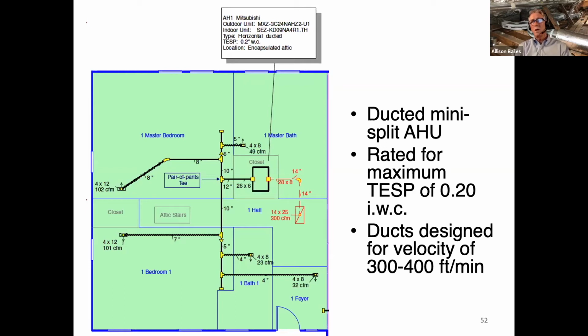It also means if you're not designing for this low velocity, you should make sure that your ducts are in conditioned space or semi-conditioned space. Mine are in an encapsulated attic. Well, nobody would ever put them into an unconditioned attic, right? Actually, the people who put them in unconditioned attics usually don't do real design, so they're not on this program.